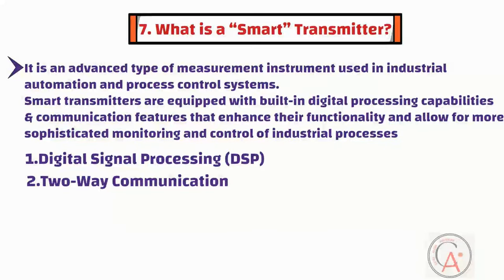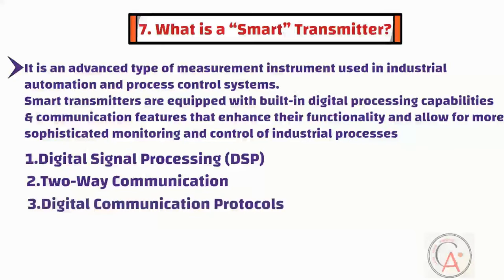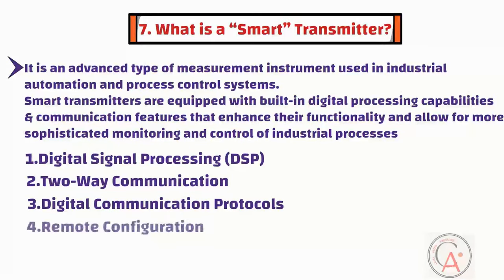The third characteristic is digital communication protocols. Smart transmitters typically support digital communication protocols such as HART (Highway Addressable Remote Transducer) or Foundation Fieldbus. These protocols enable bi-directional communication over the same wiring used for the analog signal. The fourth characteristic is remote configuration. Operators and technicians can remotely configure and calibrate smart transmitters using digital communication protocols, eliminating the need for manual adjustments in the field, saving time and reducing the risk of errors.